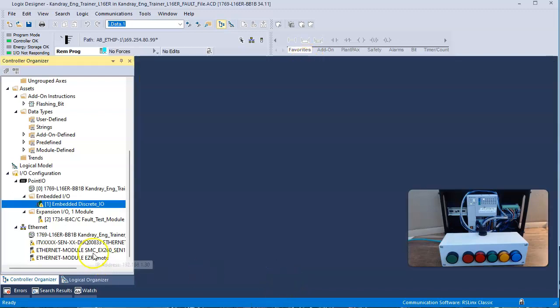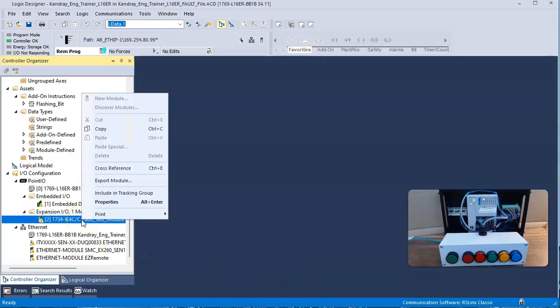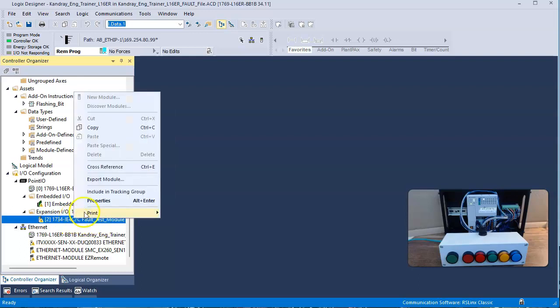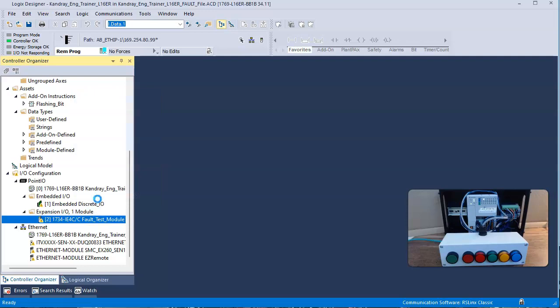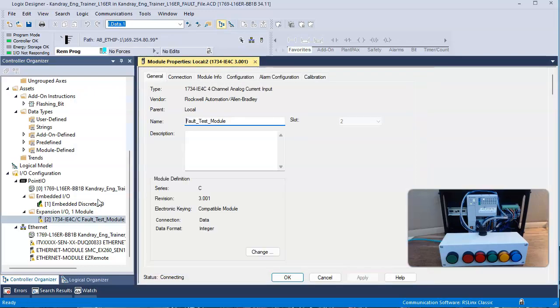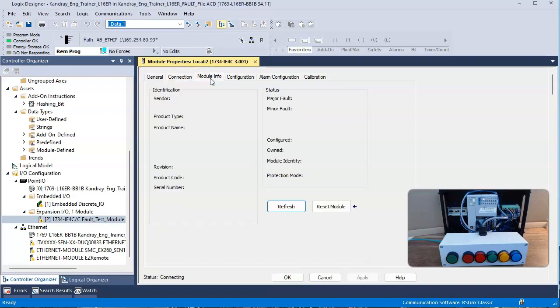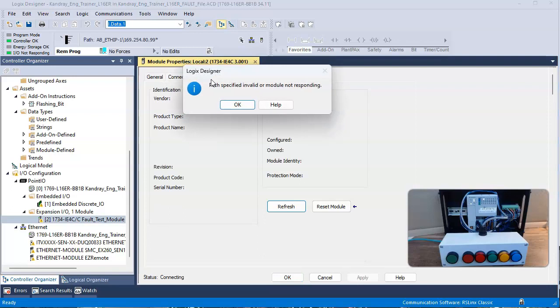So I'm going to say OK. I'm going to go down to this module, and I'm a little suspicious because this module is called fault test. So I got a sneaky suspicion this is going to be the problem, and I'm going to go over to connection. And I look at module, and it says path specified invalid or module not responding. So I'm having an issue with this module.